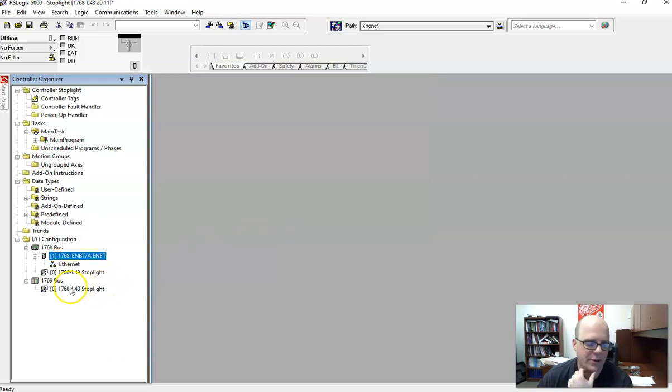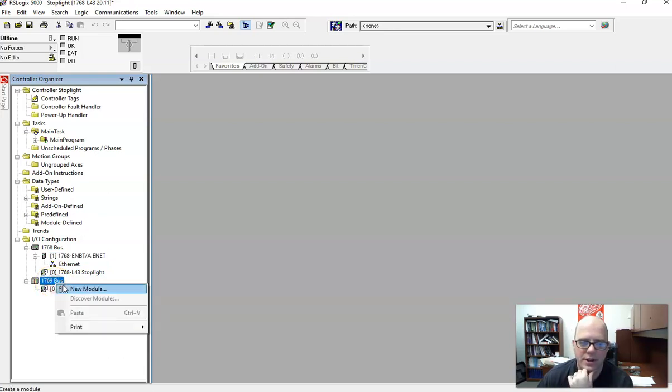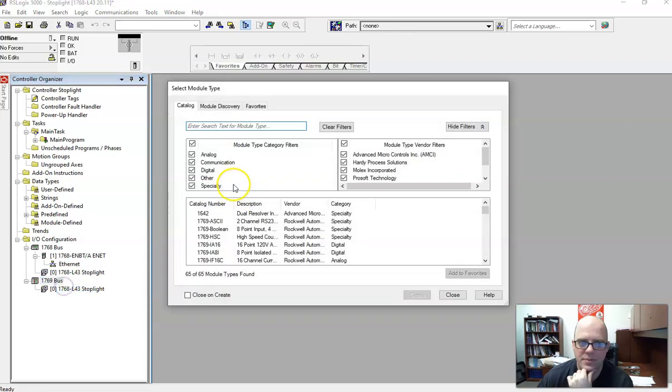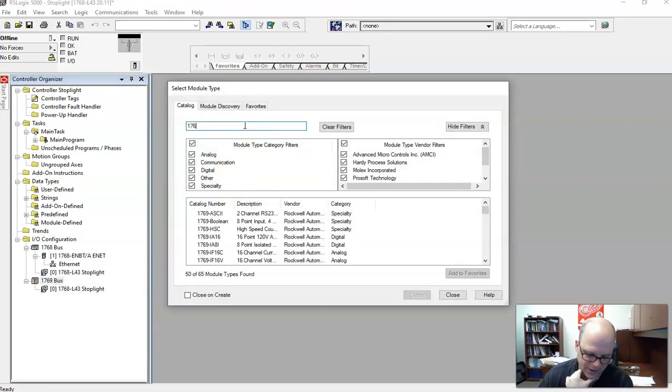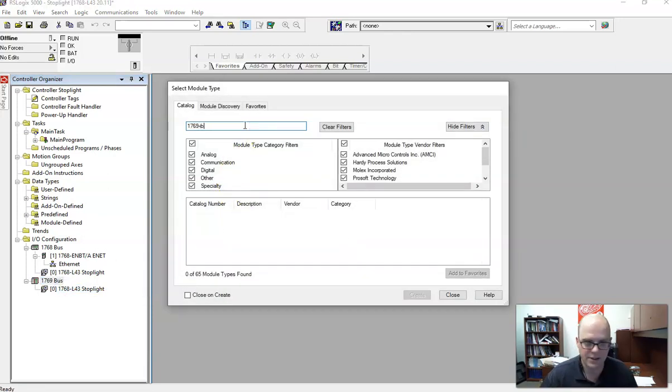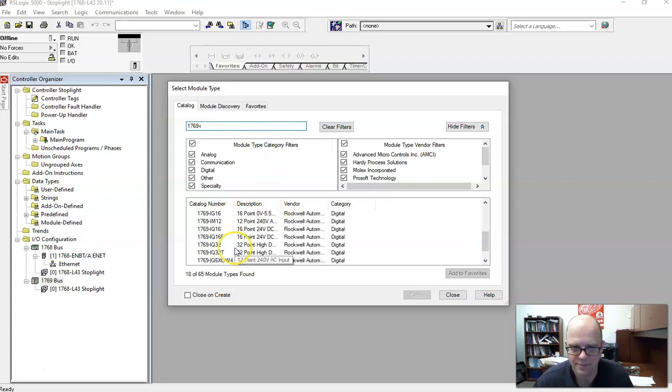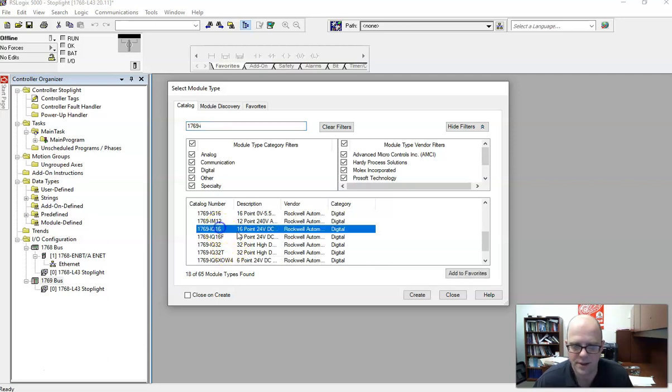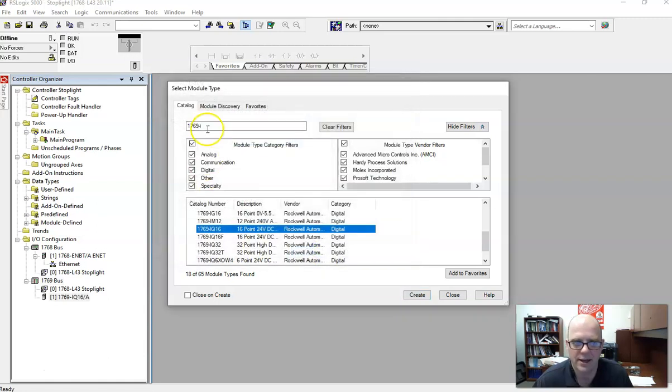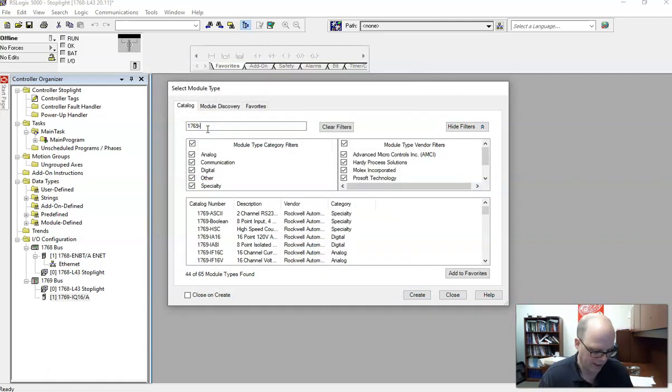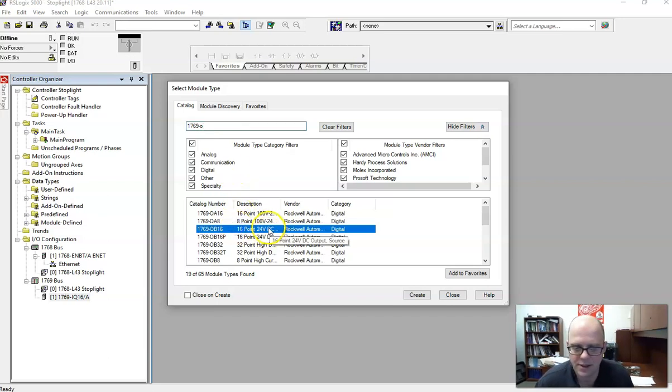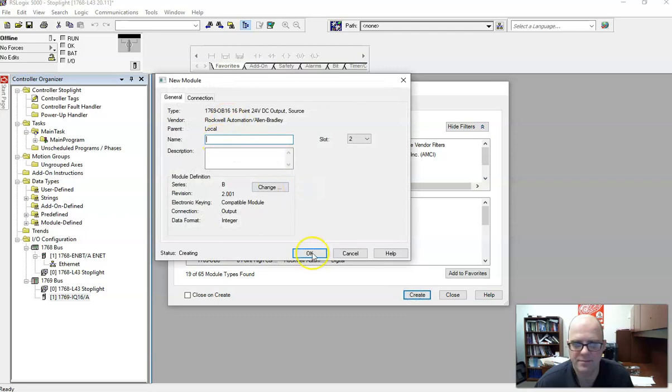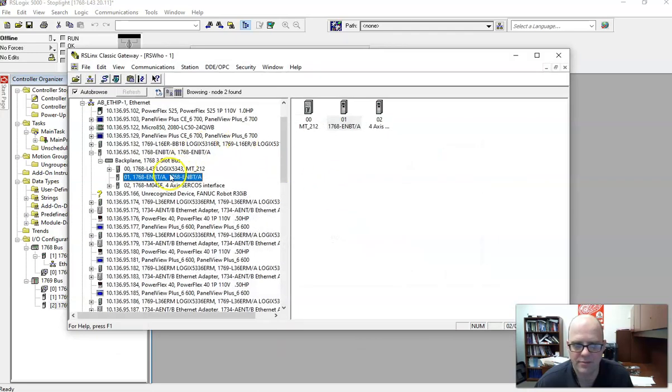So the next thing we need to add are I.O. cards. So that's on the 1769 bus. This is unique because it's got two different style buses. So right-click, New Module, and you can just type in 1769 IA16. No, IQ16. That's what it is. IQ16. Hit Create. You can give it a name. You can match a revision. You're probably safe by just hitting OK. And do the same thing with the output card. OB16 is right here. You create. And if you want to double check all that, you can go into the 1769 bus.